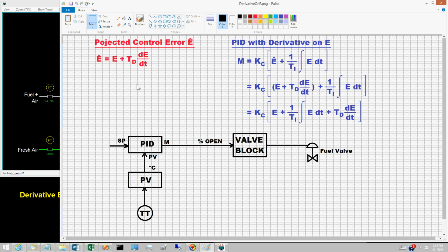The issues that arise when computing dPV/dt also arise when computing dE/dt. But for dE/dt there is an additional issue. Specifically, dE/dt reflects the rate of change of the set point as well as the rate of change of the PV. Except for abnormal events such as equipment malfunctions, abrupt changes in the PV do not occur in process applications. But abrupt changes of the set point occur routinely.